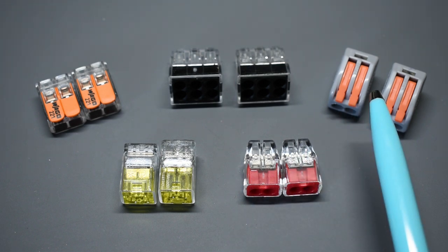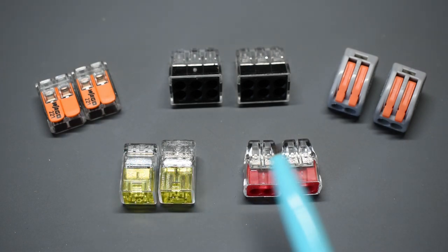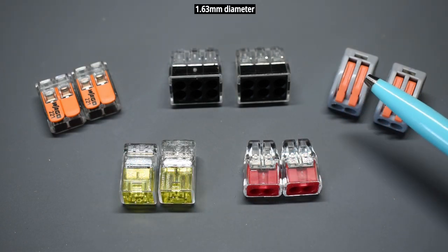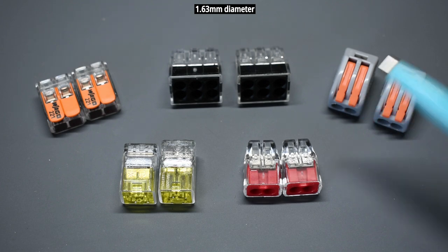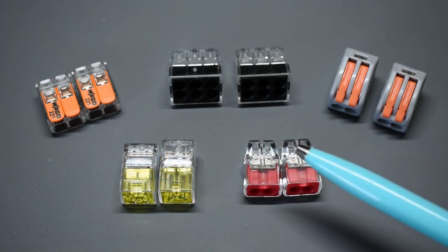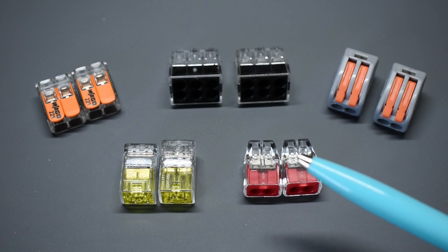They all have a limit, I believe, of 12 gauge. So for the test we're going to be using 14 gauge wire. I wanted to keep it just a little bit lower than the high end to get an idea of how well it will also do for smaller conductors. The majority of you are not going to be going below 14 gauge because that's the wire size if you're going to be connecting to a 15 amp breaker.